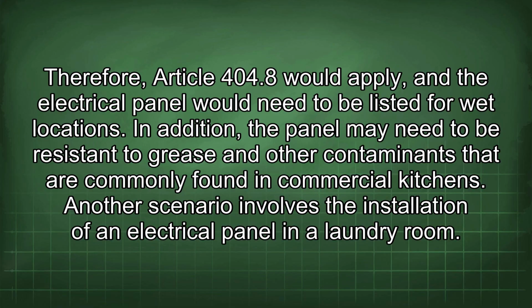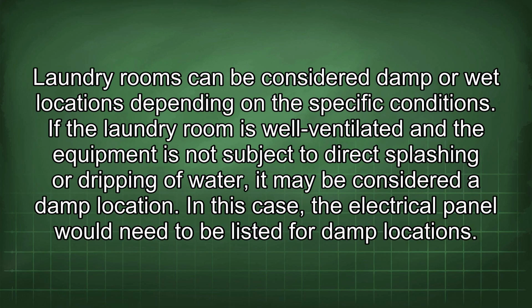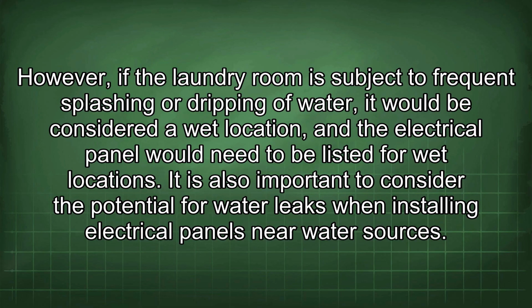Another scenario involves the installation of an electrical panel in a laundry room. Laundry rooms can be considered damp or wet locations depending on the specific conditions. If the laundry room is well ventilated and the equipment is not subject to direct splashing or dripping of water, it may be considered a damp location. In this case, the electrical panel would need to be listed for damp locations. However, if the laundry room is subject to frequent splashing or dripping of water, it would be considered a wet location, and the electrical panel would need to be listed for wet locations.